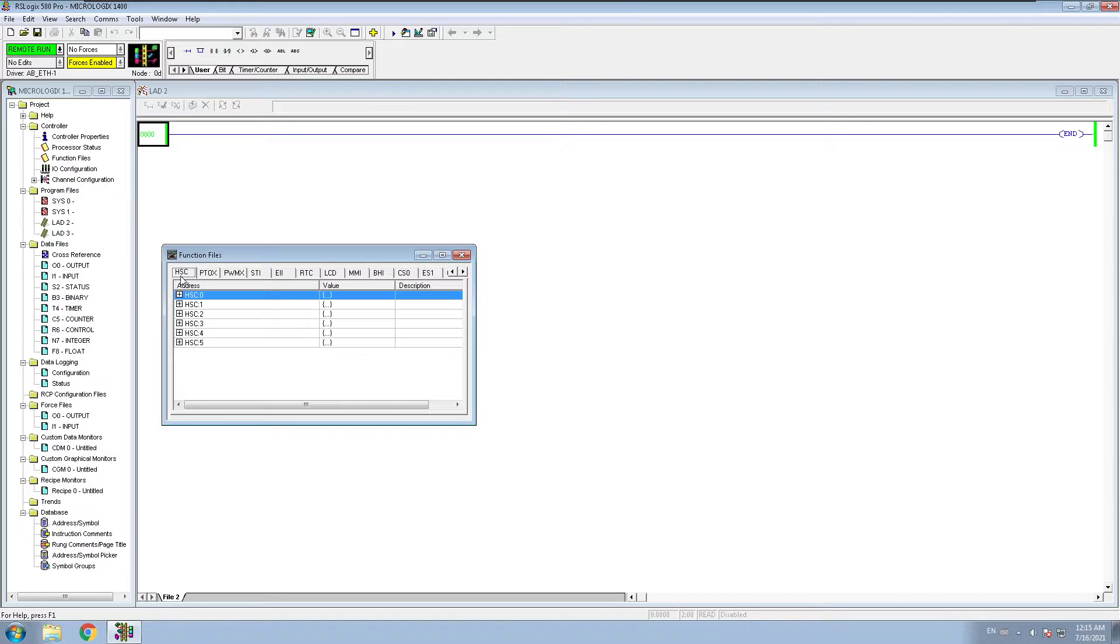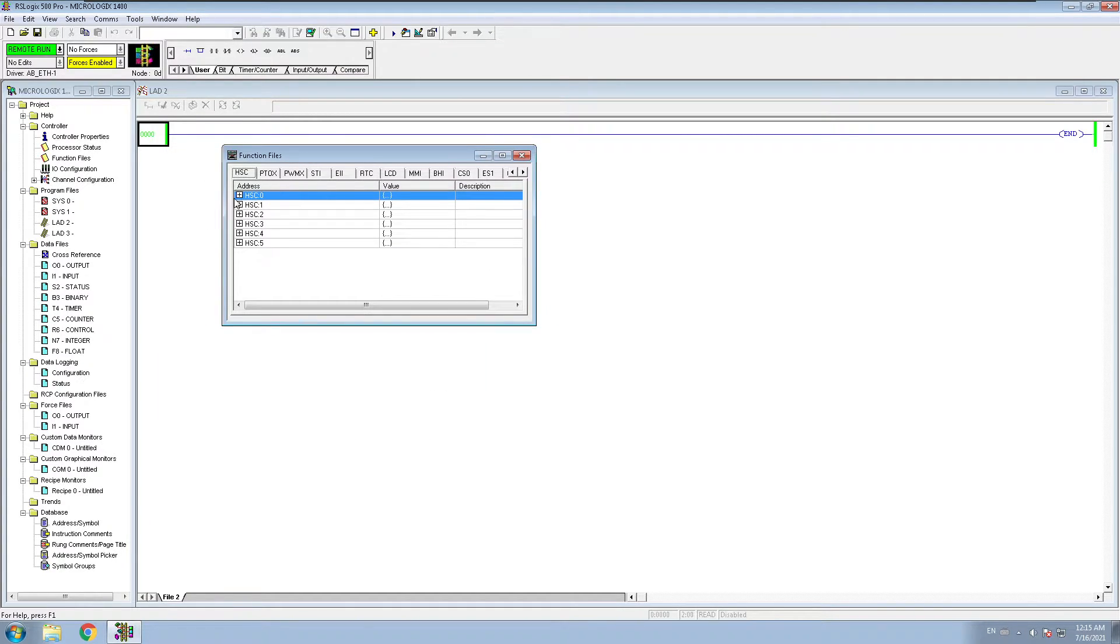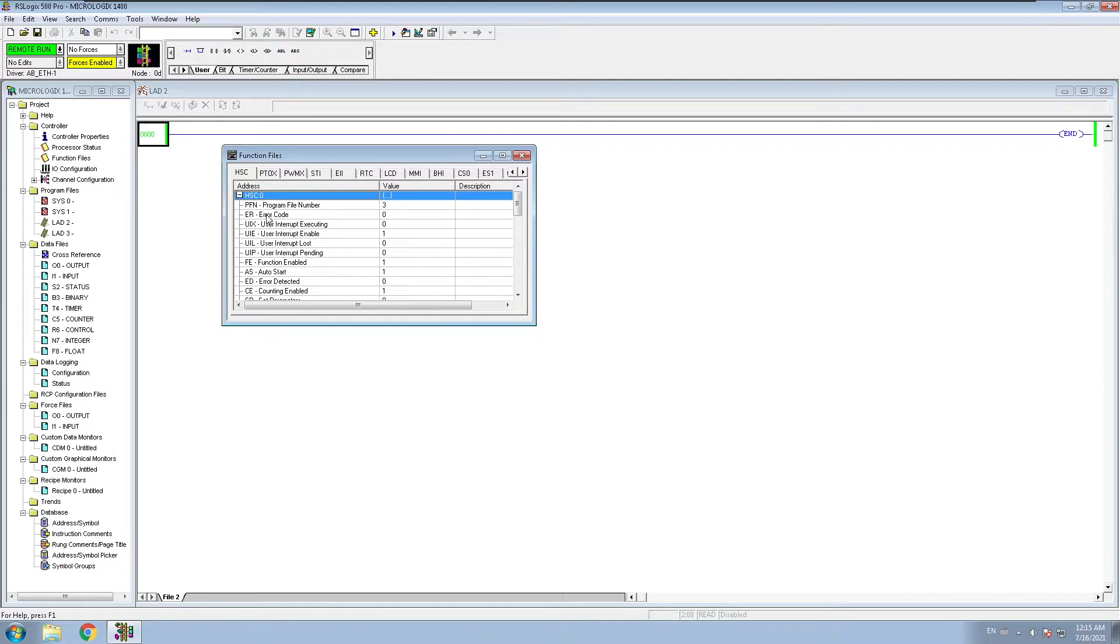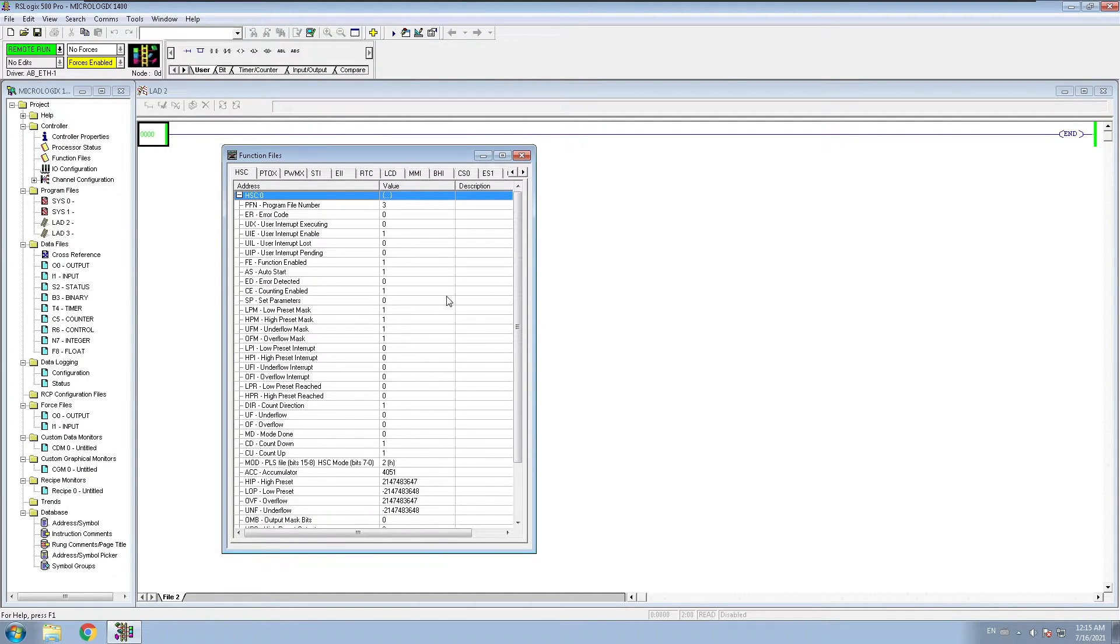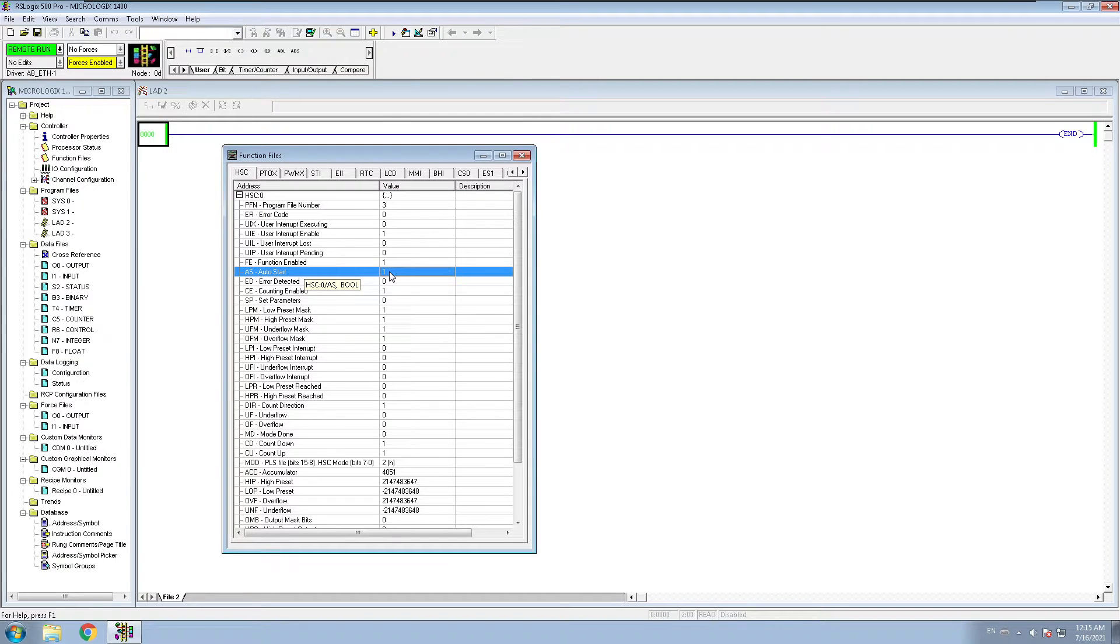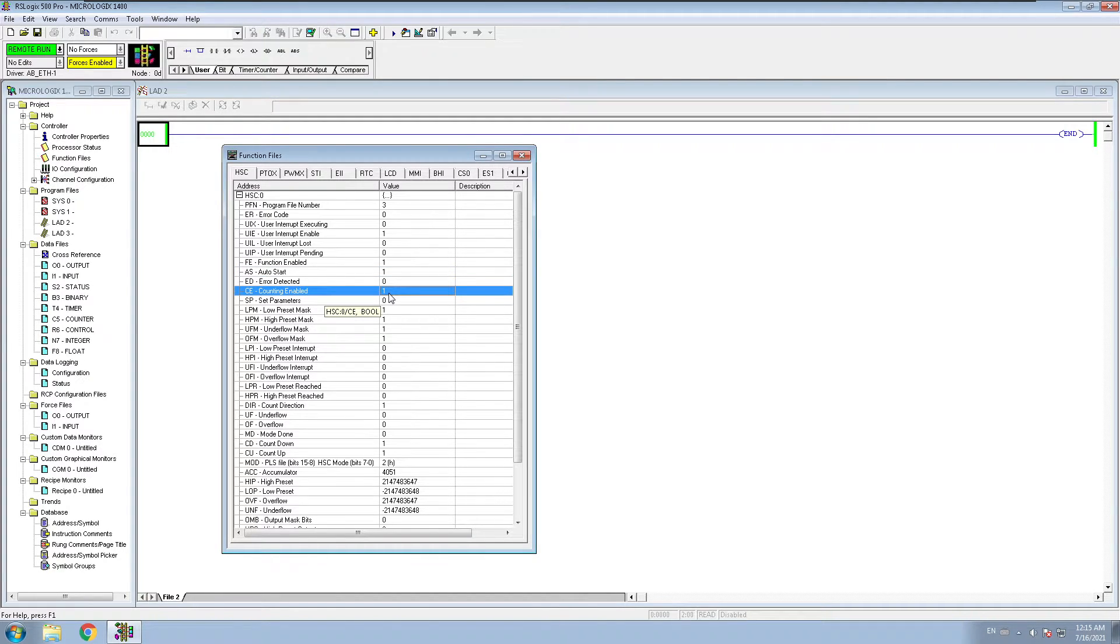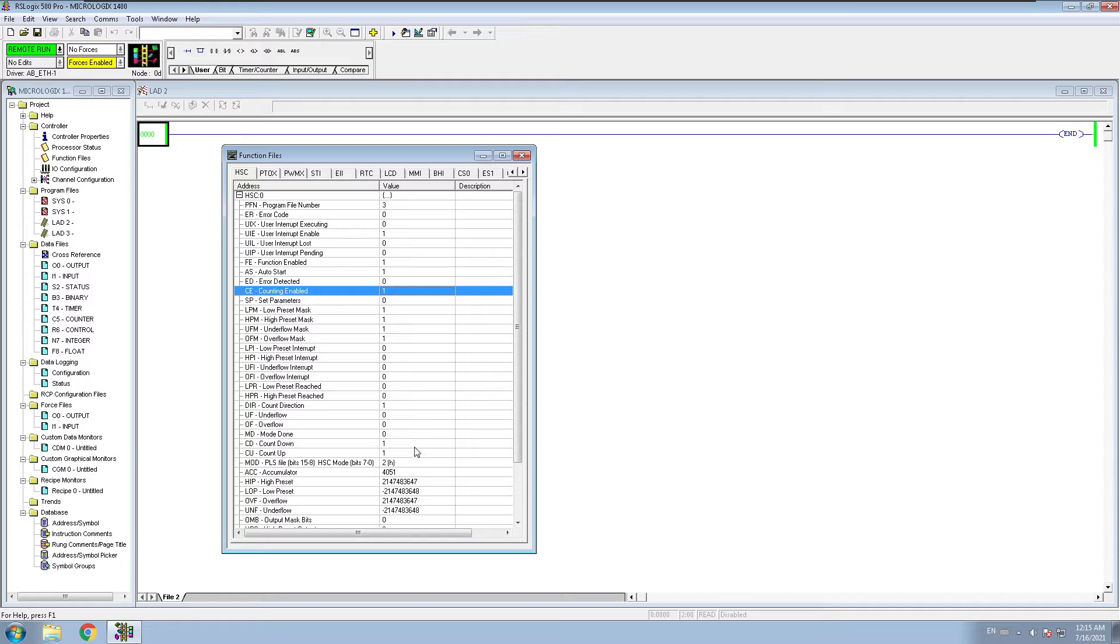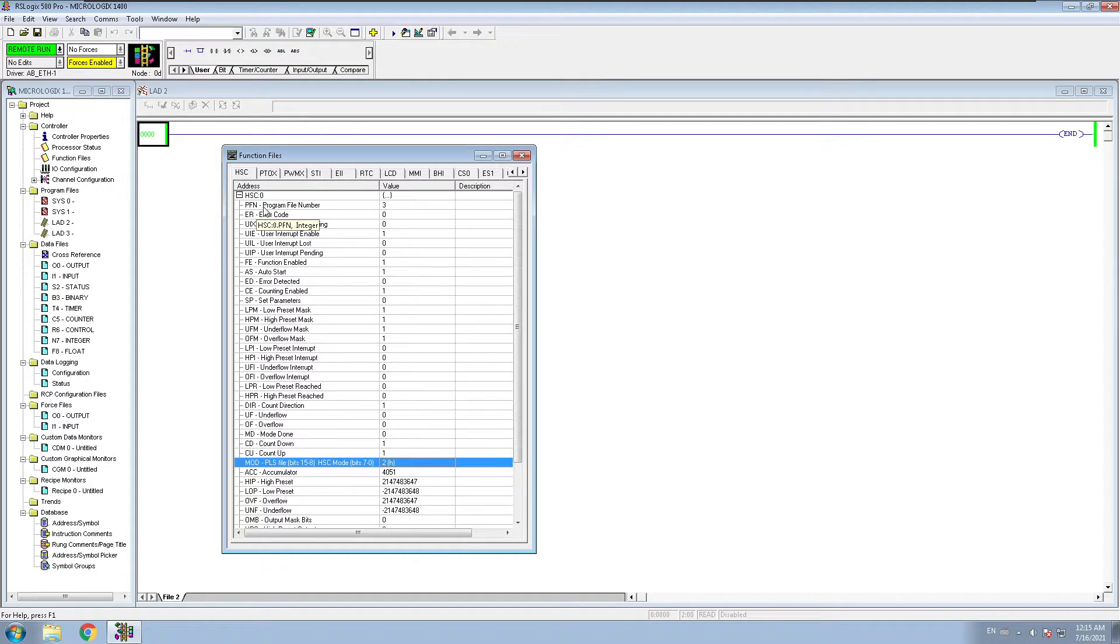You go to function files. If you're using your high-speed counter number zero, let's expand this. You have to make sure your auto start is on, which is number one. You have to make sure your counting enable is also one.